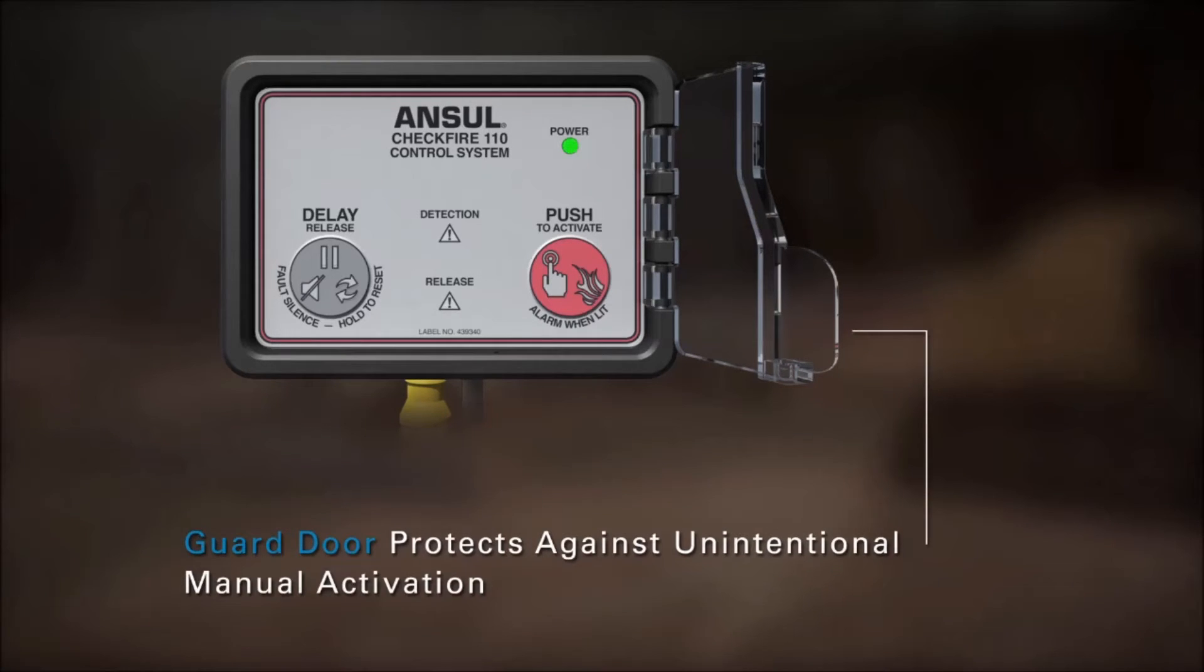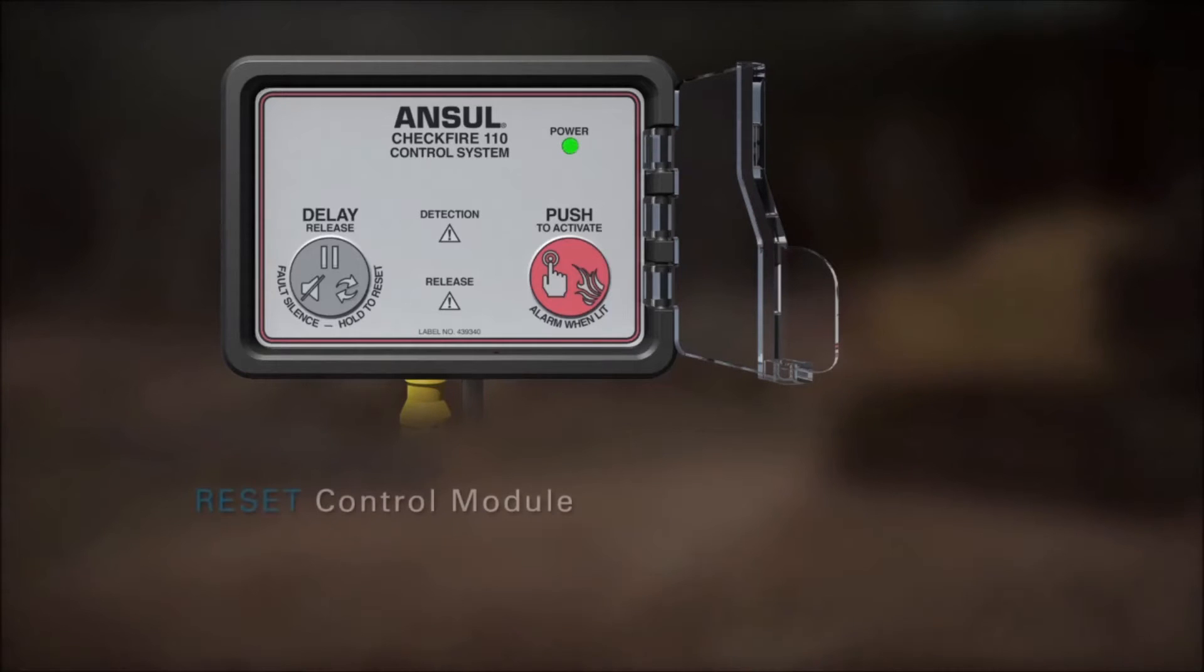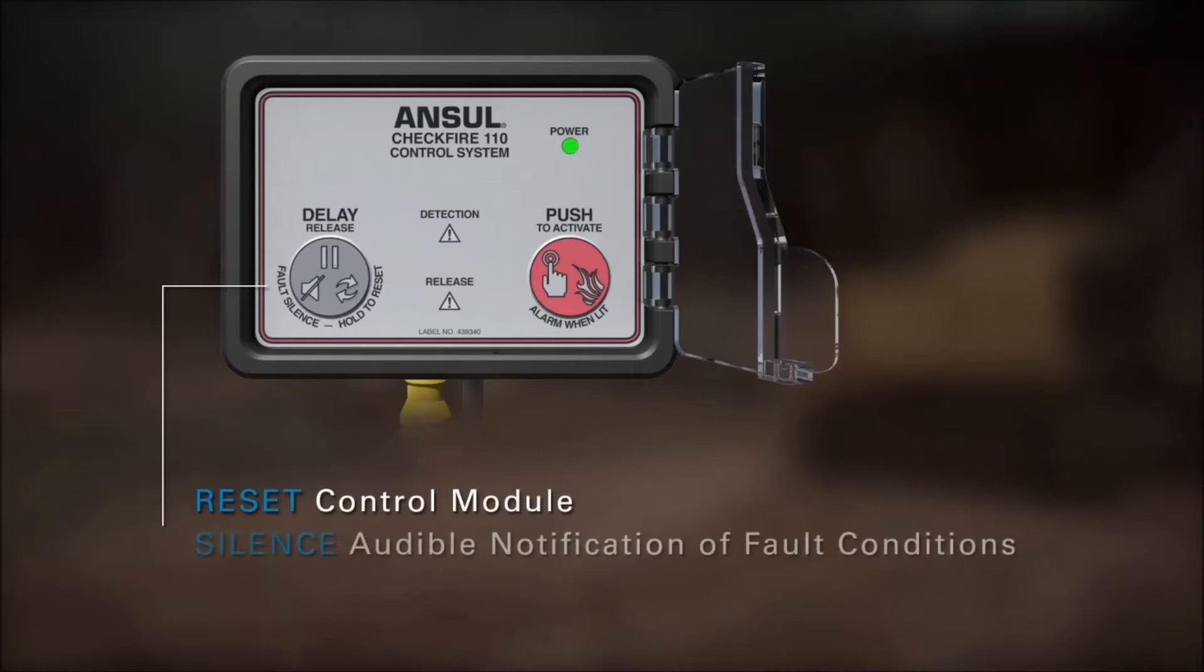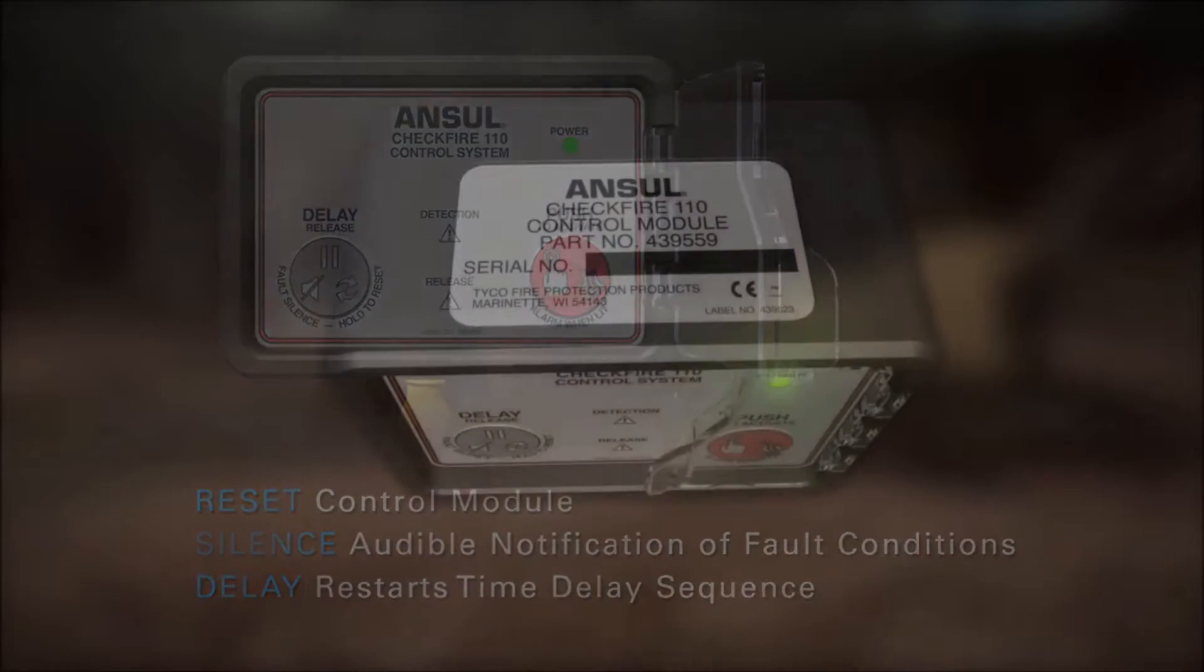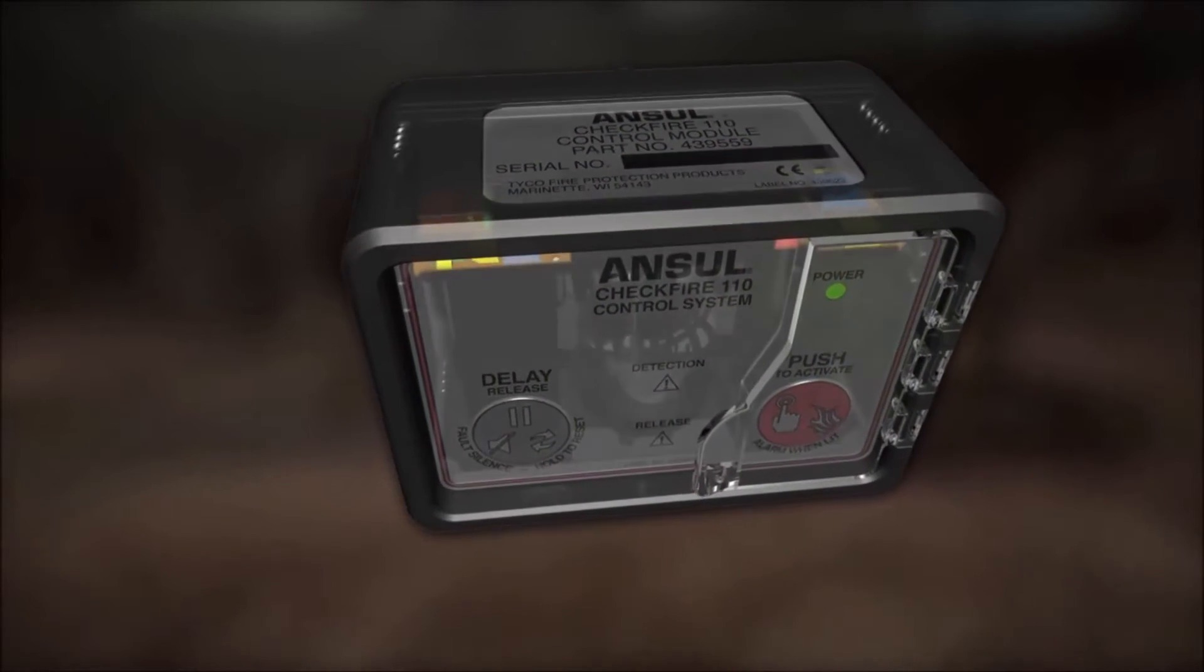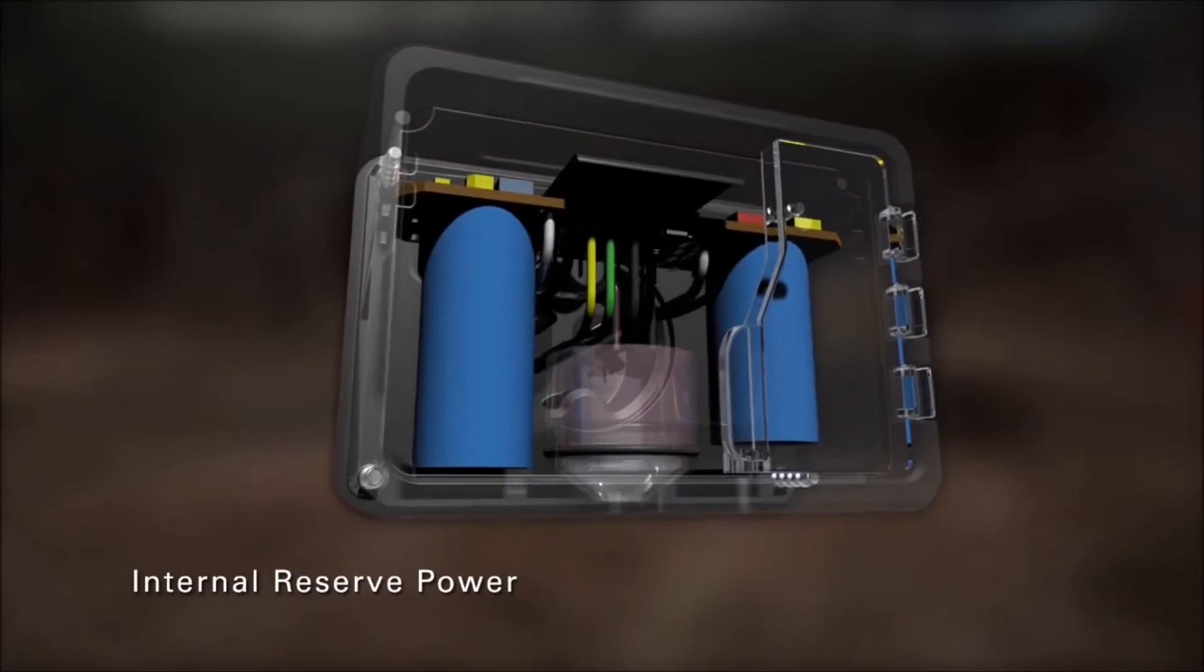The CheckFire 110 control module features a single button to reset, silence, or delay system release. If primary power from the vehicle is lost, the control module has an internal power source that is able to provide reserve power for up to 72 hours.